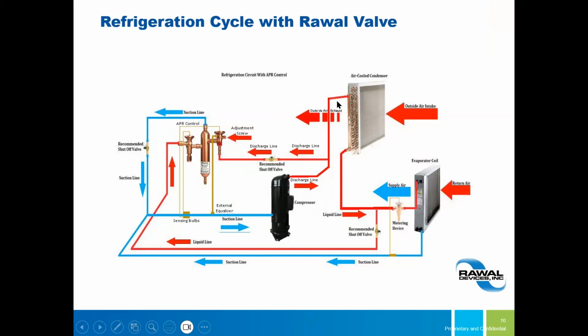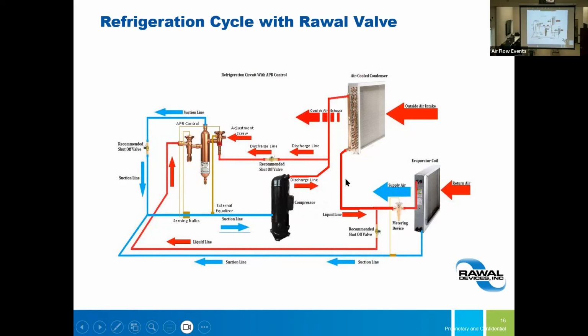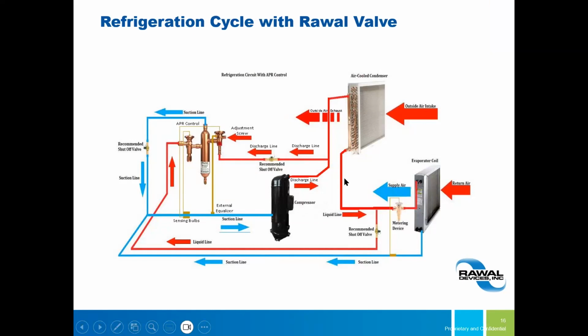So essentially, you see the condenser and the line coming off the condenser, and that's the liquid line, right? I'm sorry, my terminology is all off here. You see the liquid line coming out of the condenser after it condenses, off the bottom of the coil, right? Sorry about this. So you go down here and then you turn to the right, and then you go down to the T, right? And then there's a shut off valve for the Rawal valve, so you can shut off and isolate it. Then follow the liquid line down, and then you see it come right up.